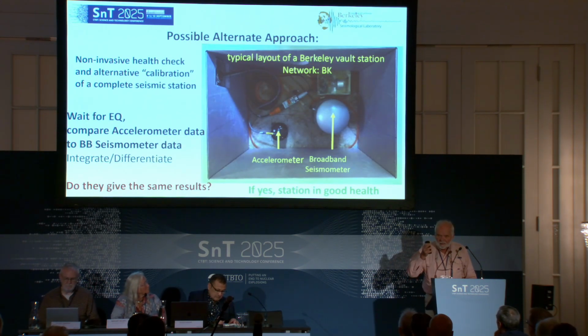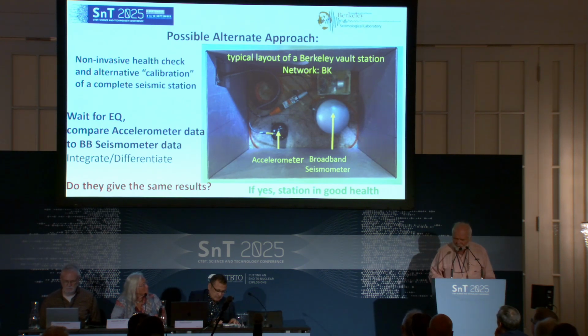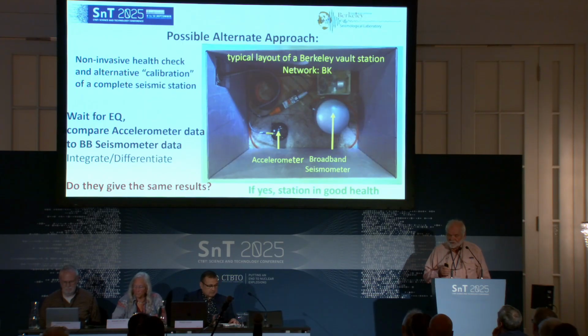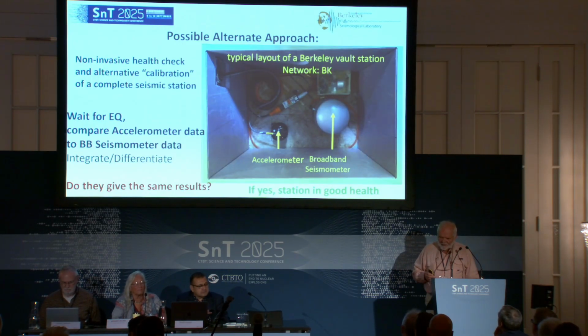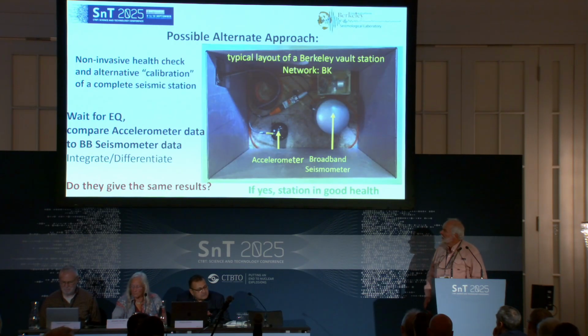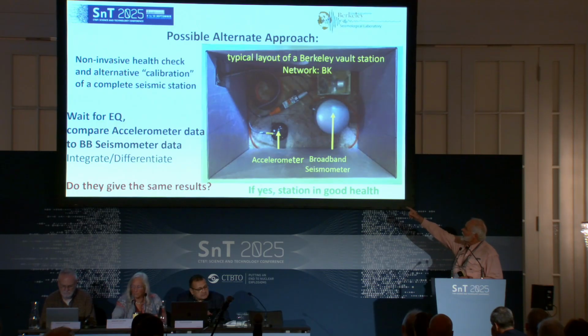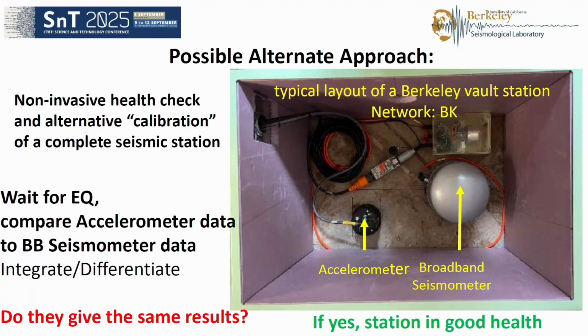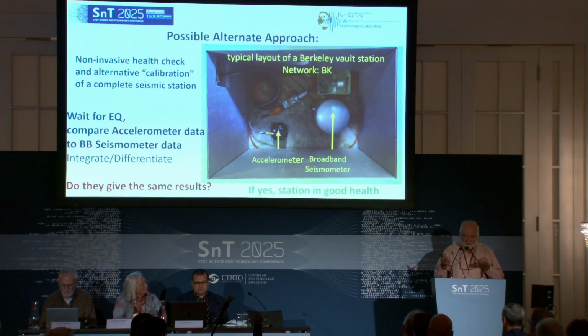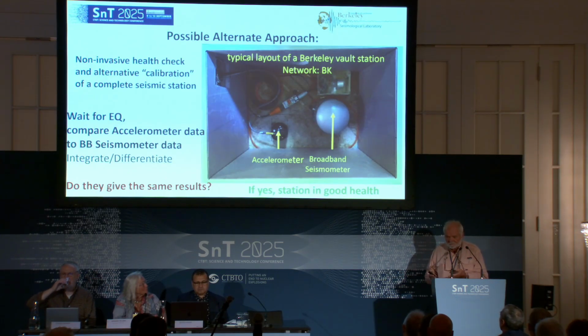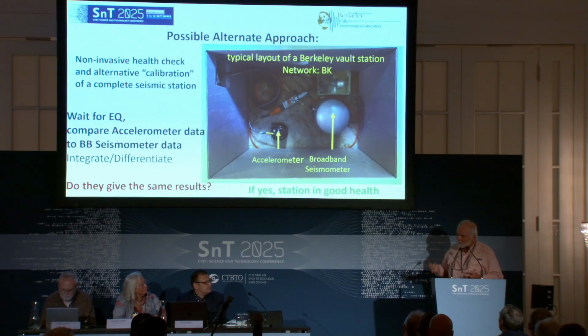As an example, and I think Nick mentioned that yesterday in one talk, in Berkeley we use a non-invasive health check, and it's sort of an alternative calibration method. When you look at the picture, you see the broadband seismometer on the right, and then we always have a co-located accelerometer, which is this black device on the left. And we just wait for an earthquake, because we have enough in California. Then we take the measurements of both of these instruments and either integrate or differentiate, and thereby we get two wave trains that are supposed to represent the same ground motion in a coherent fashion, because they are only a foot or two apart.